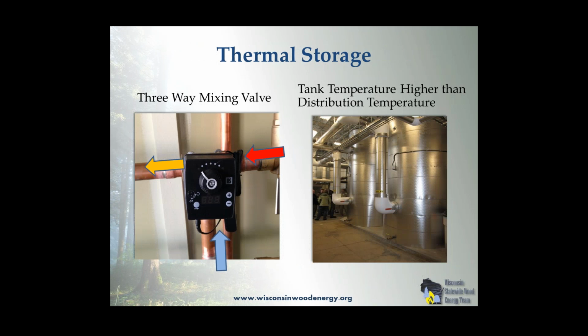One of the real problems we run into is people confuse thermal storage with thermal mass. Thermal storage is, by definition, that temperature that you store water at or store energy at that's above the planned delivery temperature. So if you wanted to distribute water at 170 and you were storing at 190, you would blend it, take some out of the tank, and mix it with the return water from the system, a little mixing valve. The little mixing valve you see here is on a 100,000 BTU-per-hour boiler, but it demonstrates the point that the blue arrow at the bottom is return water coming back. The red is being drawn in from the thermal storage tank at a higher temperature than what's mixed going out, and the yellow is the mixed energy that's going to the system to be delivered.